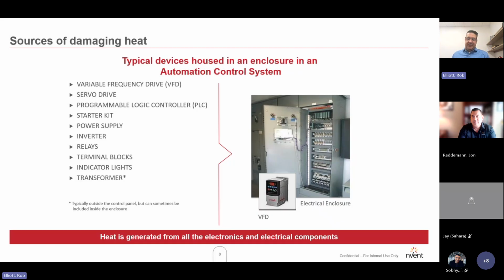But like you said, they could have additive effects because you could have that unit on the side adding more heat to that component, and that's just generating more heat inside the enclosure. And something to really take into consideration is if you look at the size of a 10 horsepower drive from even 10 or 15 years ago, as compared to the size of a 10 horsepower drive today, it was much larger than it is today, right? Yes, it is different technology today than it was 10 years ago, but you had more surface area to help dissipate heat off the components from the older drive as compared to today's drives. We don't have the surface area to help dissipate the heat away from the IGBTs and the other components, making it more critical to follow spacing requirements and manage that internal heat load.